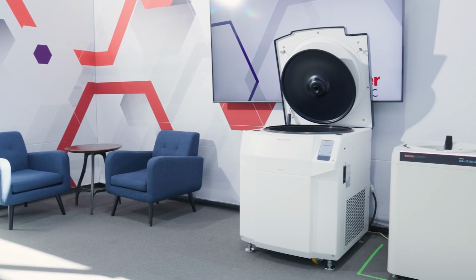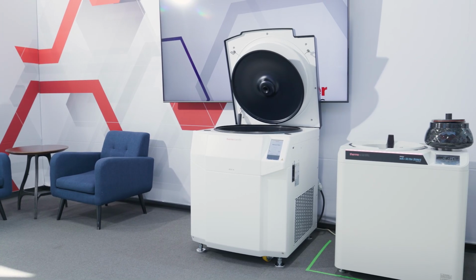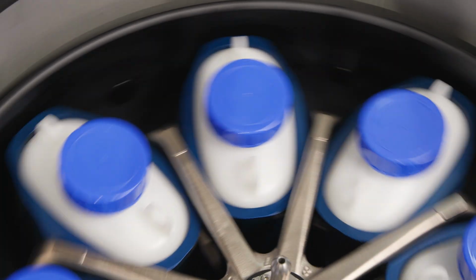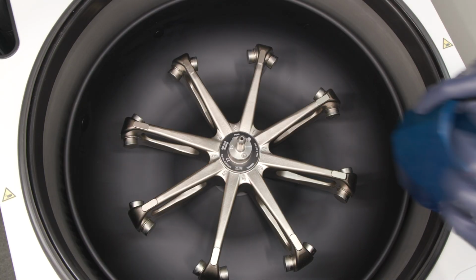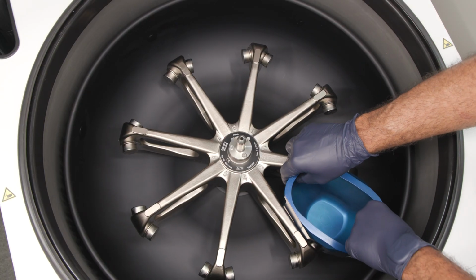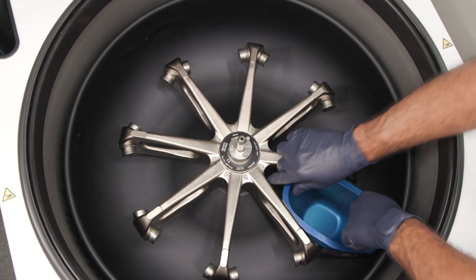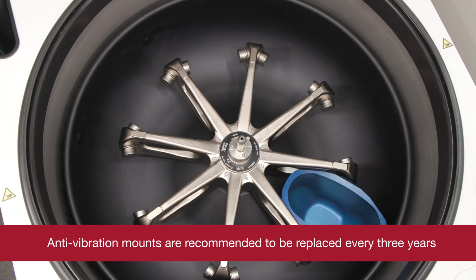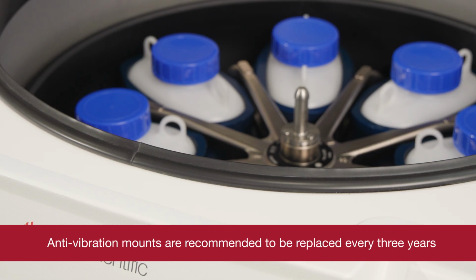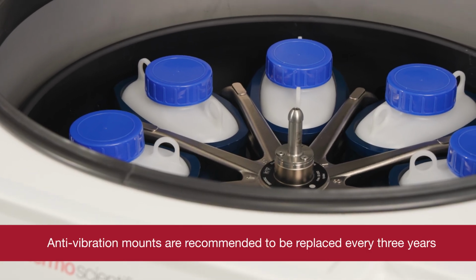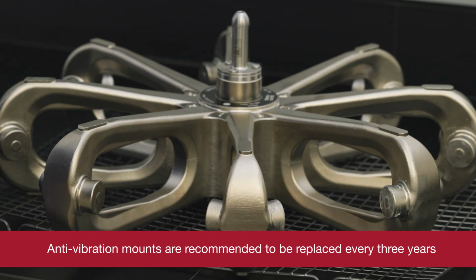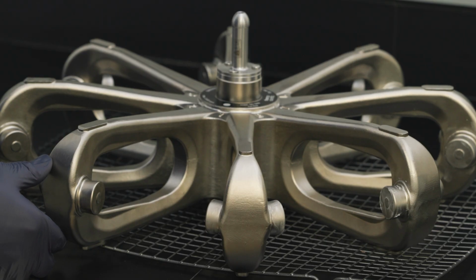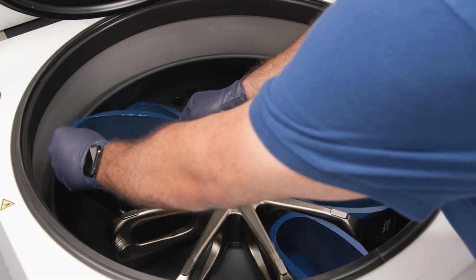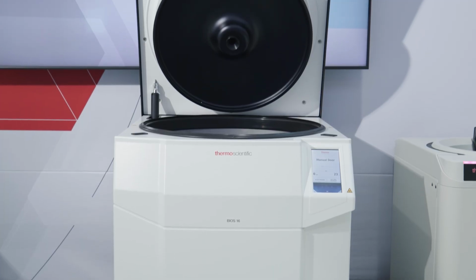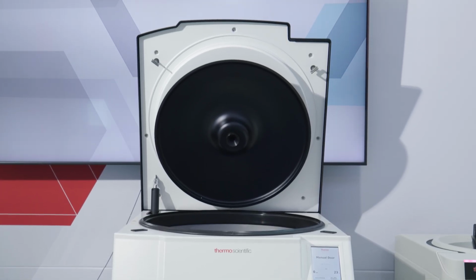To maintain the safe and reliable functionality of this product, ongoing preventative maintenance is necessary in accordance with the following recommended schedule. For rotors and accessories, follow the information found in the rotor and components chapter of the manual. Anti-vibration mounts should be replaced every 3 years, and the centrifuge itself needs to be decommissioned after 15 years or 150,000 cycles. Please have the centrifuge and its accessories serviced once a year by an authorized service technician as well.